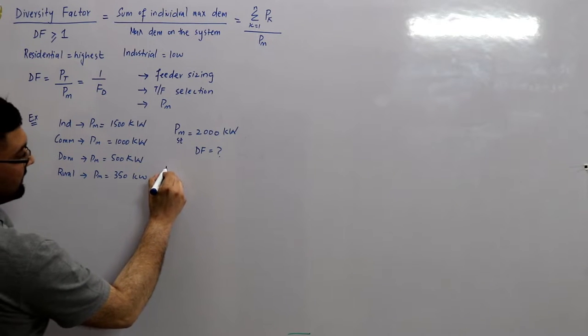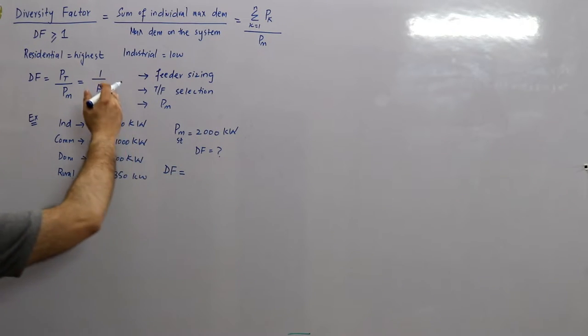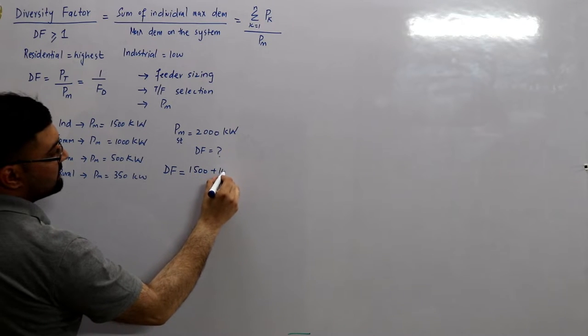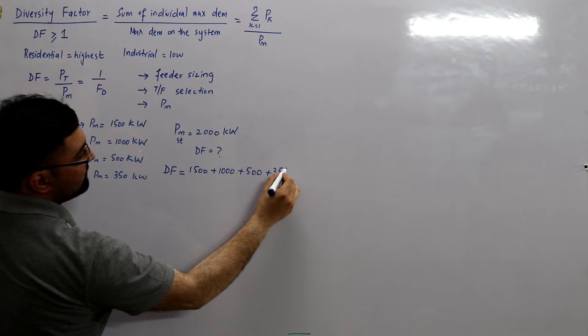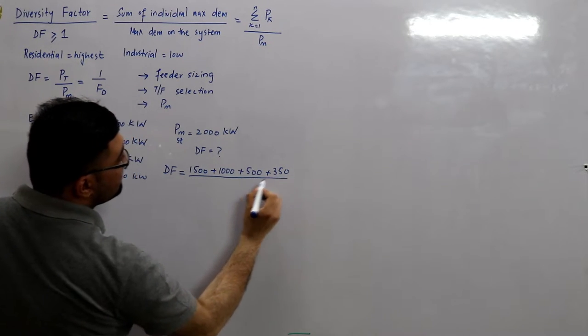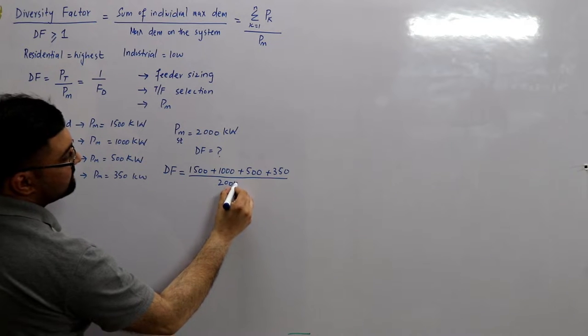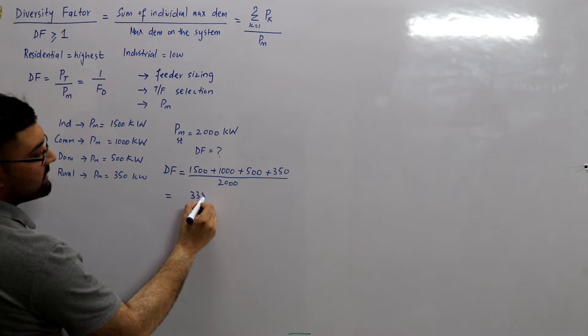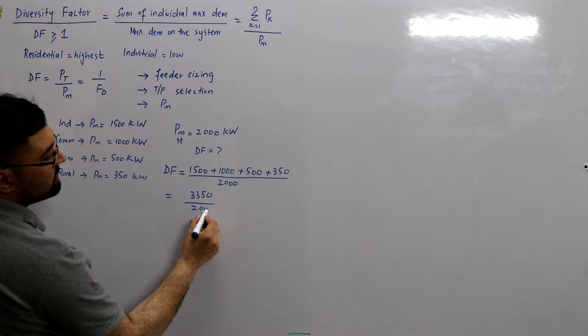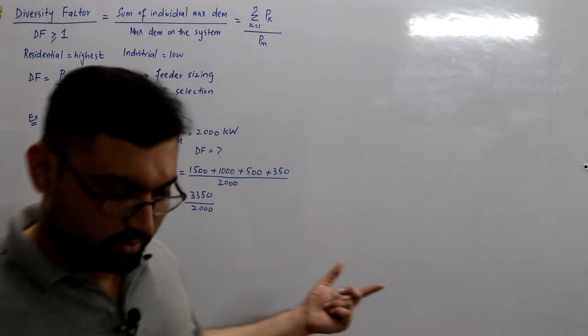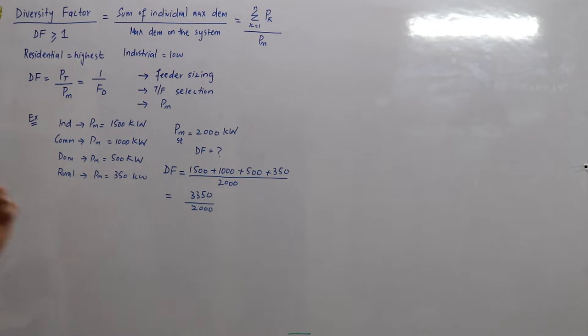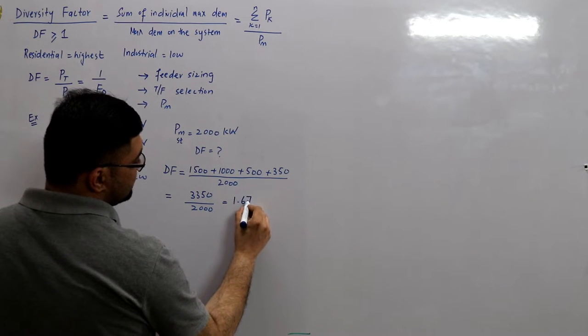From the formula, the diversity factor is the summation of individual maximum demands — 1500 + 1000 + 500 + 350 — divided by the maximum demand of the station, which is 2000. This equals 3350 divided by 2000. As expected, the summation is always greater than the system maximum demand, and this ratio comes out to be 1.67.